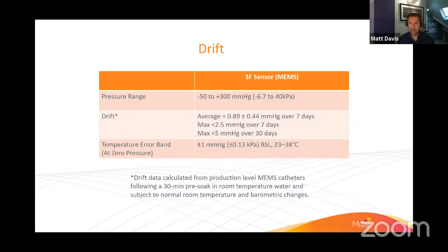The figures shown on the slide are some of the lowest drift specifications in MEMS technology on the market today. These figures are from our single-use clinical devices, and to achieve these results with reusable catheters, handling and cleaning are key, which is why Millar and ADI work together to provide our customers with robust training and support options specific to catheter care. You'll see on the middle cell, it shows drift levels of less than 1 mmHg over 7 days, with a maximum drift of 2.5 mmHg, directly due to the manufacturing processes described previously.